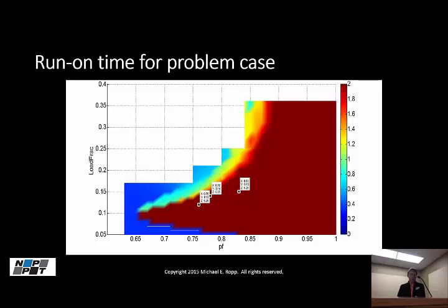So in this case, because of the interactions between the different generators, the active anti-islanding in the inverter plants could not see the island, and it ran on for a long time. So this was a case where direct transfer trip would have been required. And the way it works then is the last guy in pays for the direct transfer trip. So there were 2 PV plants and the sync gen that were all grandfathered in. When the 3rd plant came in, that's where this study got triggered and they got flagged.